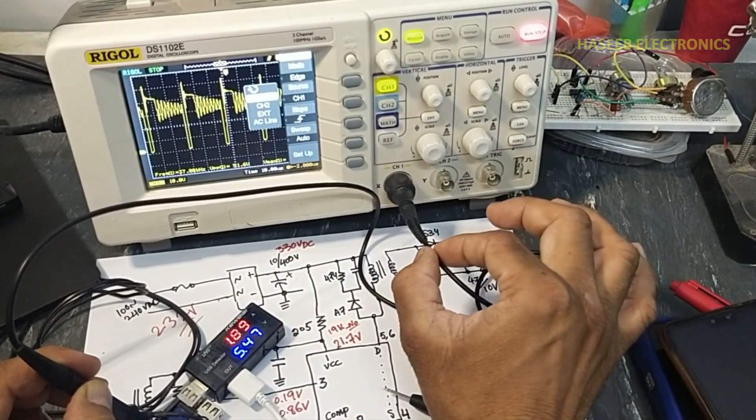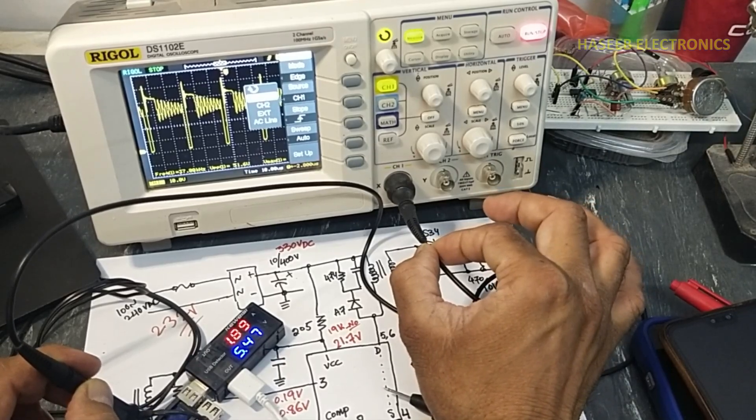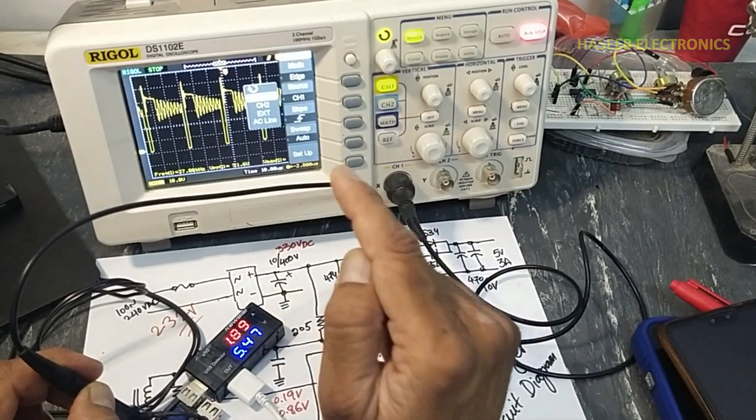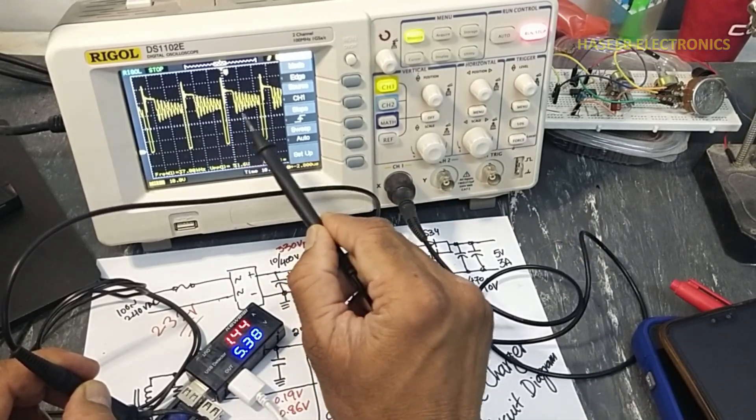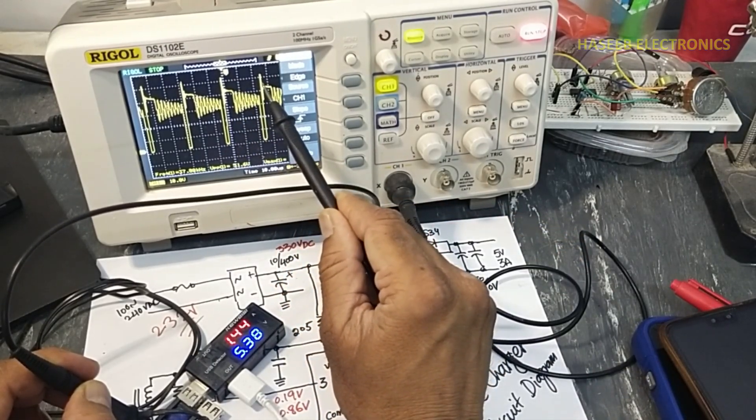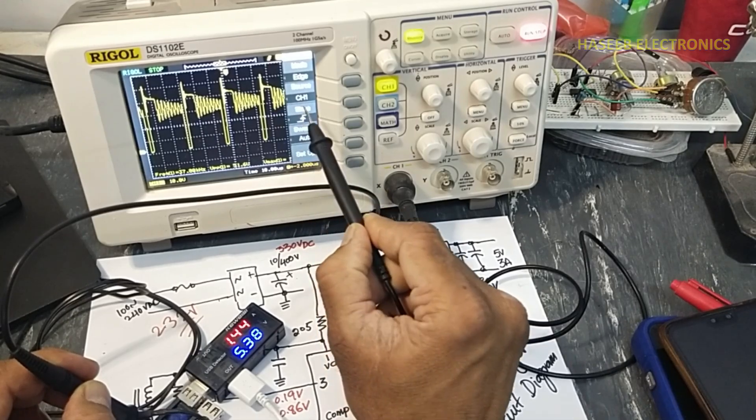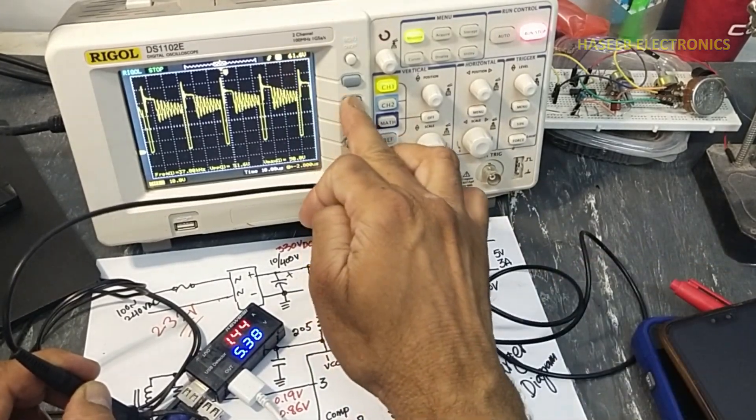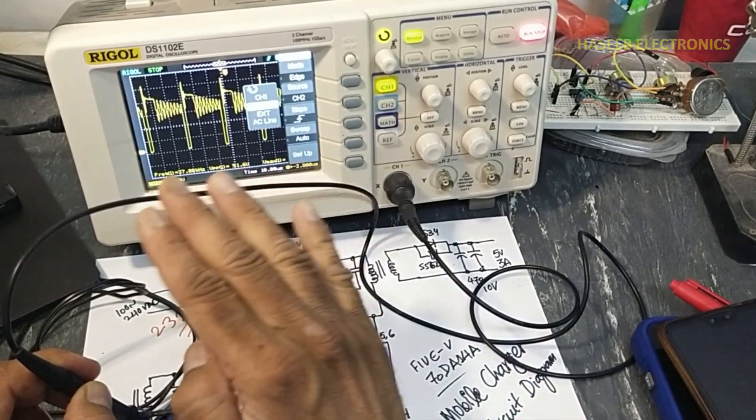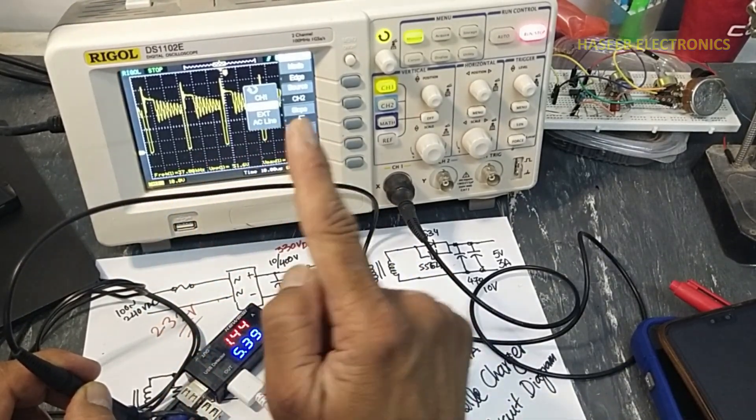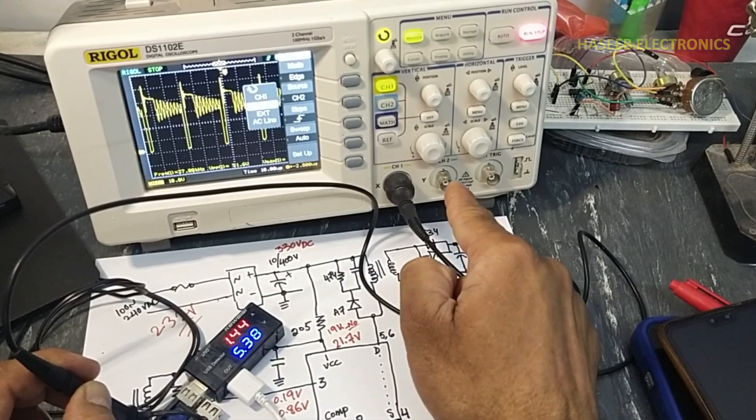The very important thing is from which source we are triggering. If we are using signal at channel number one, from same signal we want to trigger it. This signal is coming at channel one, it will start to record that pulse from here. So we say channel number one. If I will select channel two, at that time its display will not stable until we provide signal at channel two.